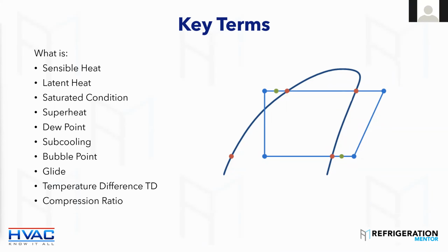Since this was a bonus, let me give a bonus trick question, if everybody's up for it. So let's say our compression ratio is 3-to-1 on a regular basis. And every time you go check that thing on a maintenance or whatever, it's 3-to-1. But one day you get a service call, you go check it, it's now 1-to-1. Most likely what has happened to that compressor?